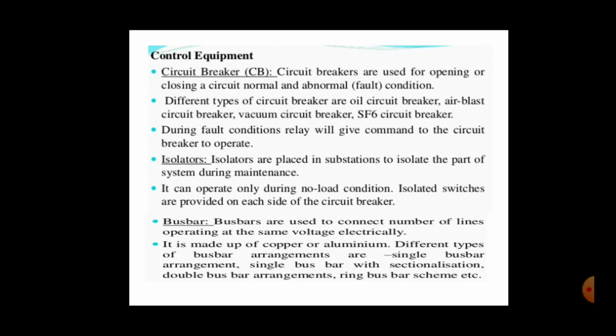Next, control equipment. Circuit breaker. Circuit breakers are used for opening or closing a circuit under normal and abnormal fault conditions. Different types of circuit breakers are oil circuit breaker, air blast circuit breaker, vacuum circuit breaker, SF6 circuit breaker. During fault conditions, the relay will give a command to the circuit breaker to operate.